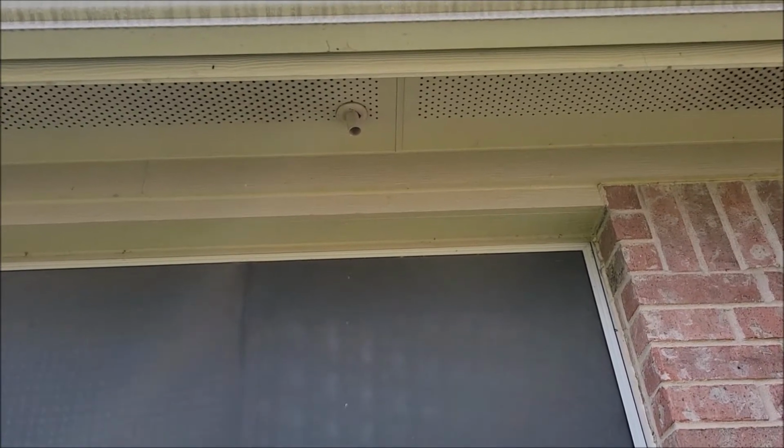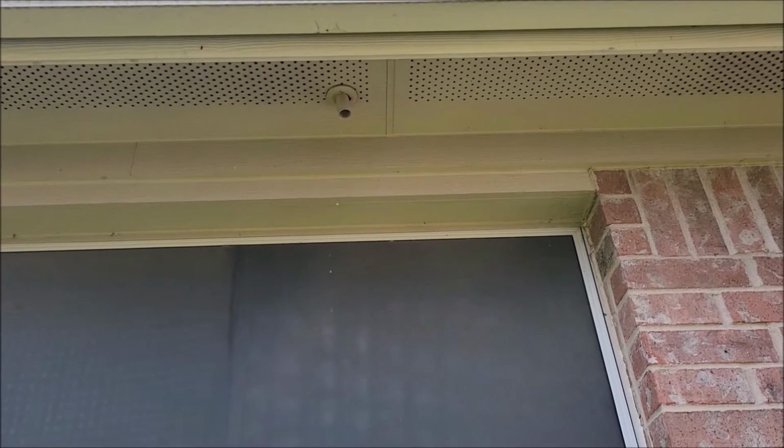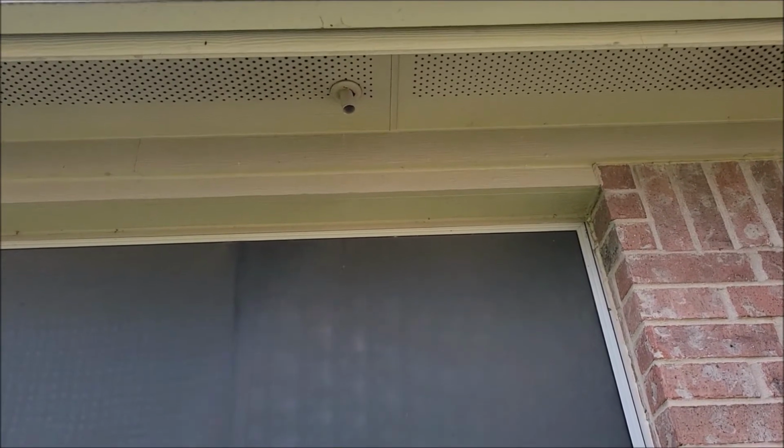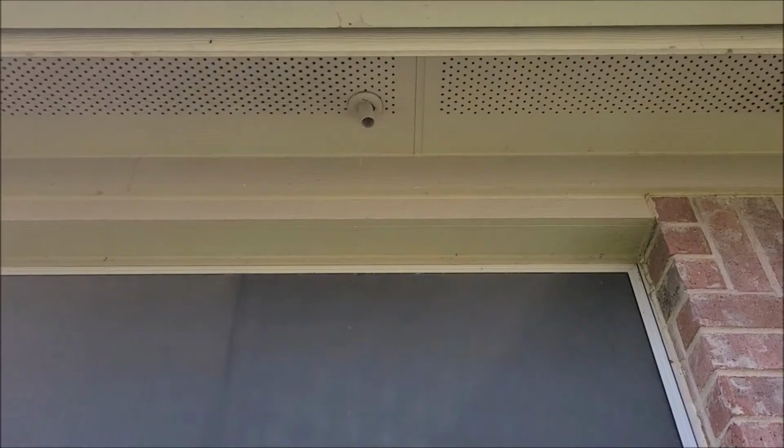So on ours, what this water dripping down right here is telling me is that the secondary drain is being used for all the humidity that's getting sucked out from the air conditioner, which should normally go to the primary drain, which is typically hooked up to a bathroom sink or something like that. There's a drain pan underneath your air conditioner's coil, which is collecting the water dripping off. It's dripping down into that pan, and that pan has two outlets. It has a primary outlet and a secondary outlet. The primary outlet will typically drip down into a sink.